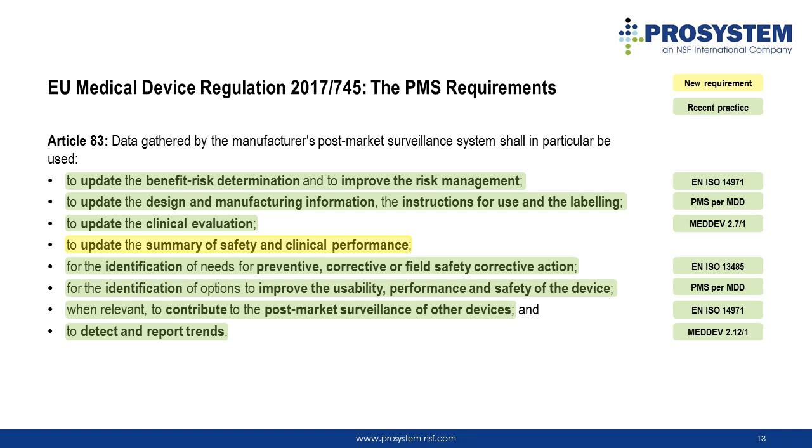But if you look at all these interfaces that are stated in Article 83, only the requirement to update the SSCP report is entirely new. All other interfaces were already required either by the Medical Device Directive, by standards such as ISO 13485 for Medical Device Quality Management System, or ISO 14971 for risk management, or by guidance documents.